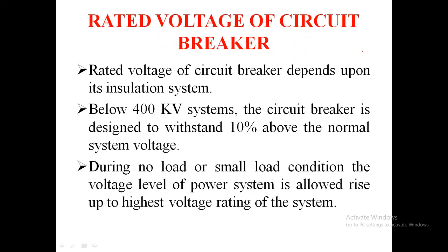And next is rated voltage. This refers to the highest system voltage for which the breaker is to be designed. It is expressed in kV as an RMS value. In a 3-phase circuit, it is the phase to phase voltage.